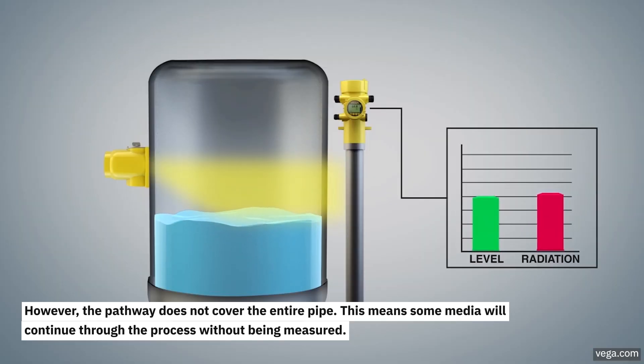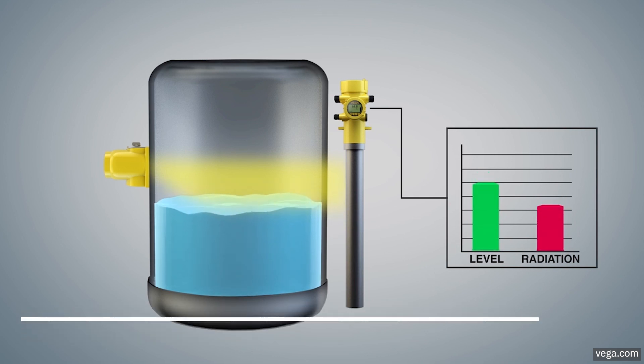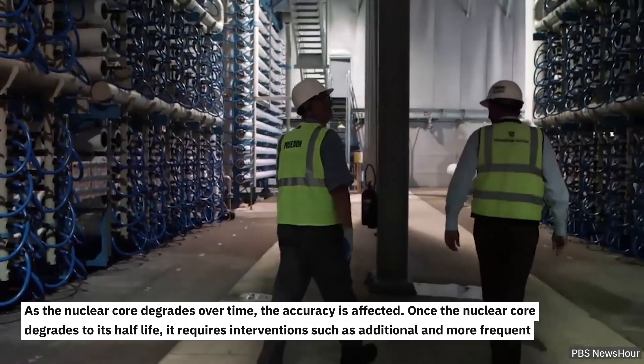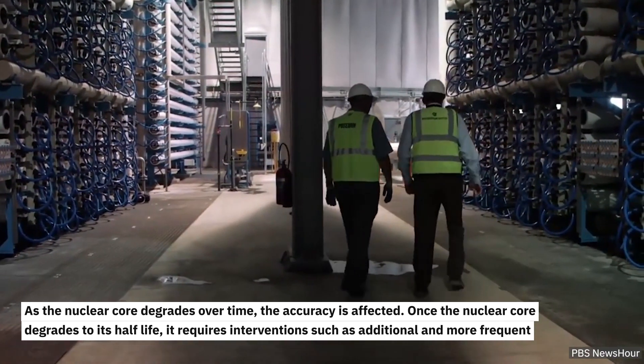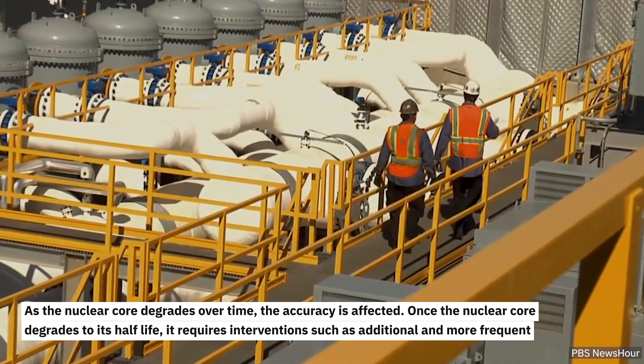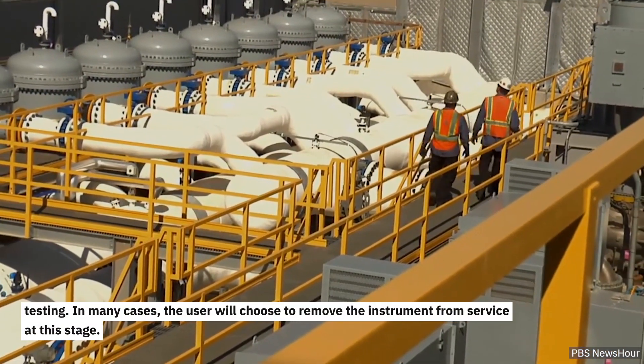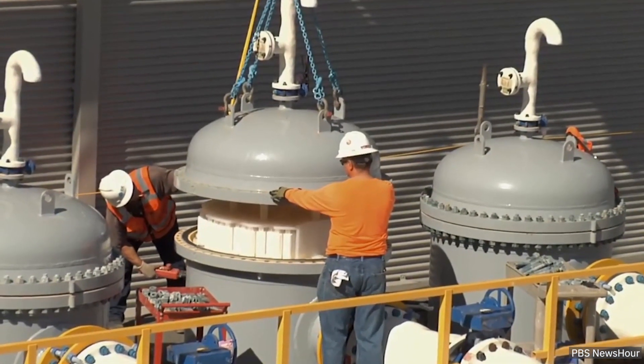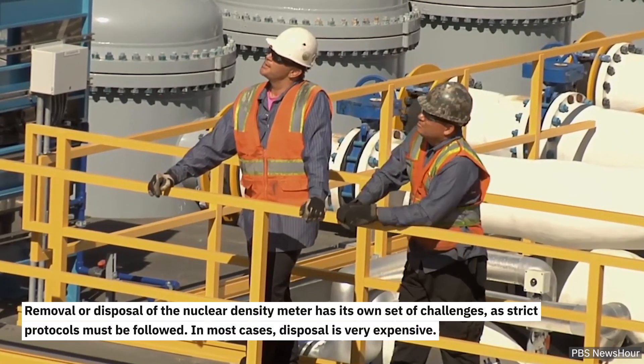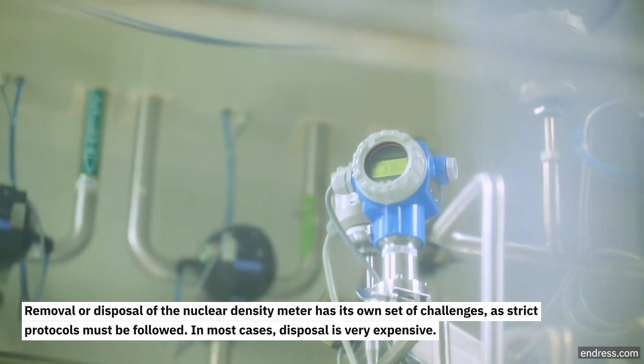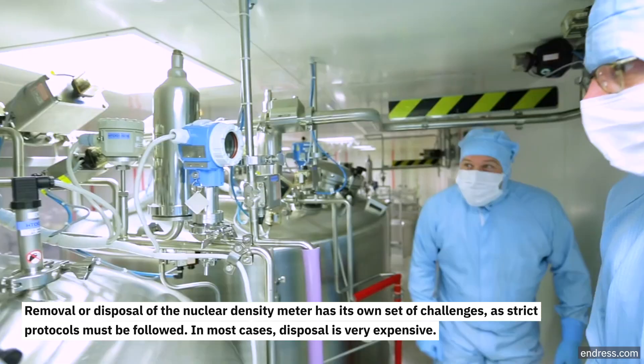As the nuclear core degrades over time, the accuracy is affected. Once the nuclear core degrades to its half-life, it requires interventions such as additional and more frequent testing. In many cases, the user will choose to remove the instrument from service at this stage. Removal or disposal of the nuclear density meter has its own set of challenges, as strict protocols must be followed. In most cases, disposal is very expensive.